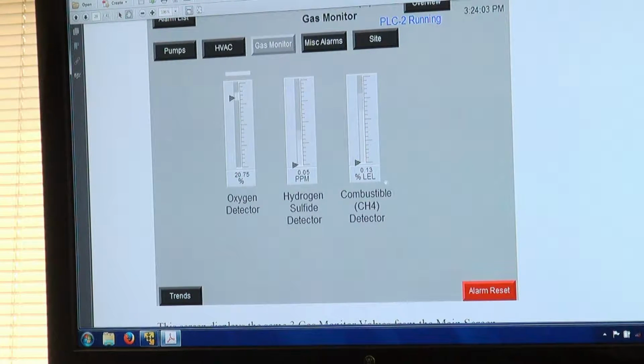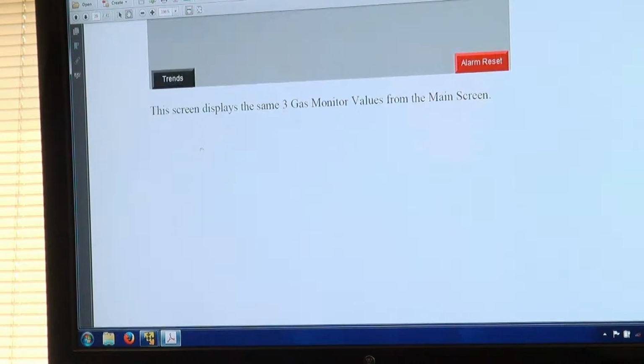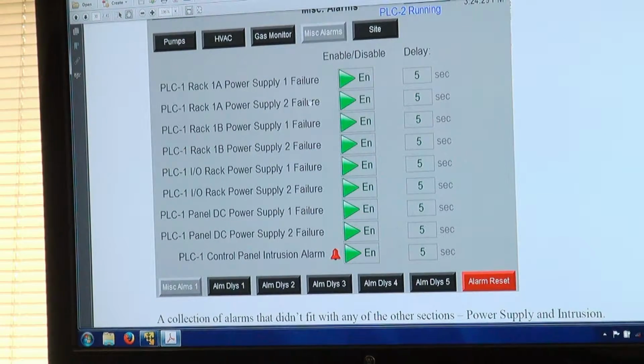Our gas monitoring is really simple. It's just a blown up view of the 3 gas things that we're monitoring. Your miscellaneous alarm, this is where I was talking about. There's lots of power supplies in there. We have 3 racks. We have our primary PLC, our secondary, and then the actual I/O. Each one of those racks has 2 power supplies associated with it. That way, if anything happens to a single power supply, nothing happens to your system. If the rack 1A, if both power supplies went out, rack 1B, which is the second processor, would take over. Seamlessly, you wouldn't notice it.